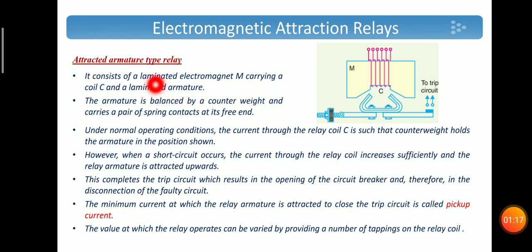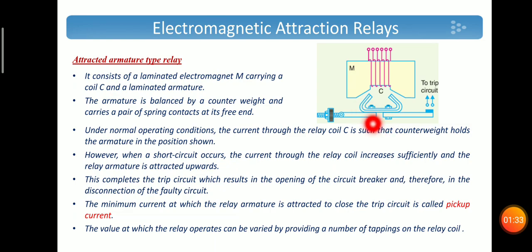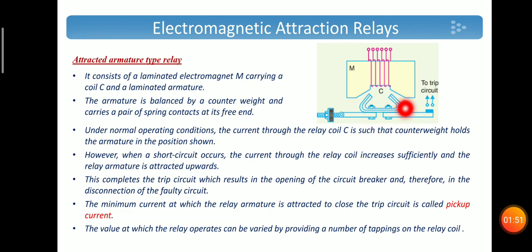In the attracted armature type, the relay consists of a laminated electromagnet carrying coil C, and the armature is balanced by a counter weight at the bottom. Here there is an electromagnet and the coil, and this is the armature balanced by the counter weight. Under normal condition, the current through coil C will not energize or attract the armature — it is balanced by the counter weight.